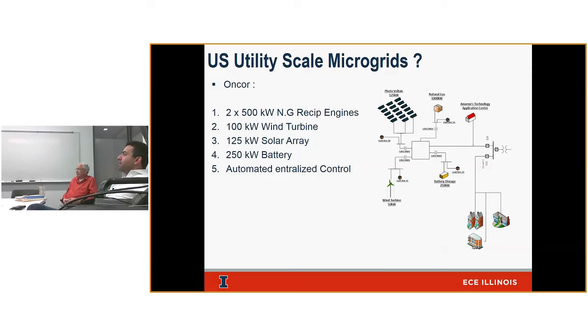But we see the wind turbine, right? So this one was, of course, different. We wanted it to be different, kind of become the most advanced microgrid in the nation. The first thing we wanted to do with the microgrid is not serve behind the meter loads. We wanted to focus on serving the distribution feeder, so we make sure we serve actual customers out of that microgrid. When we installed it, our goal was to support this circuit here. This is circuit 371. It has about 200 customers on it, about 180 residential, and the rest are commercial customers. So that was the main use case: to provide reliability to these customers out on circuit 371.